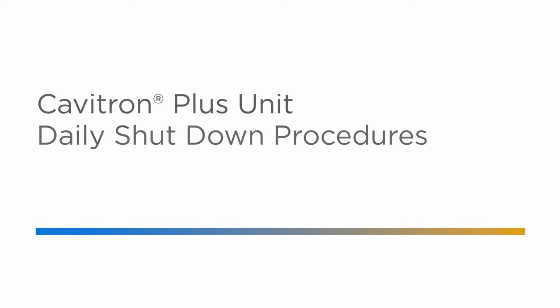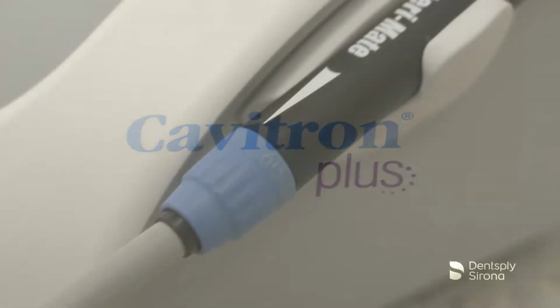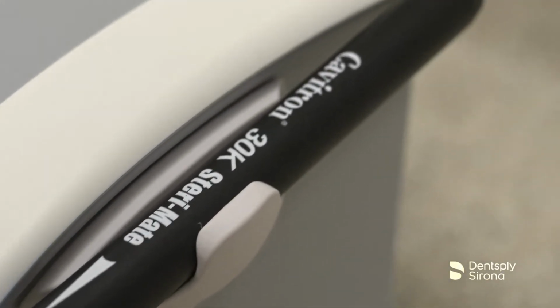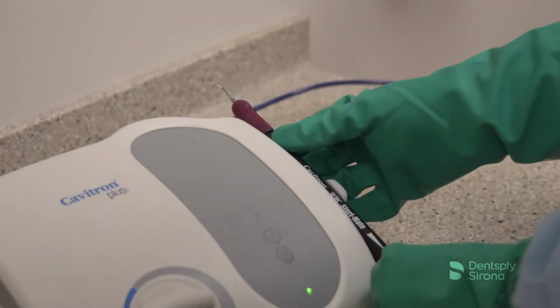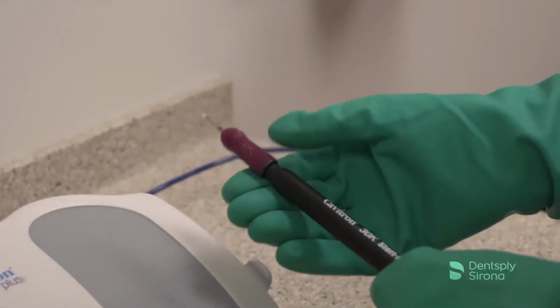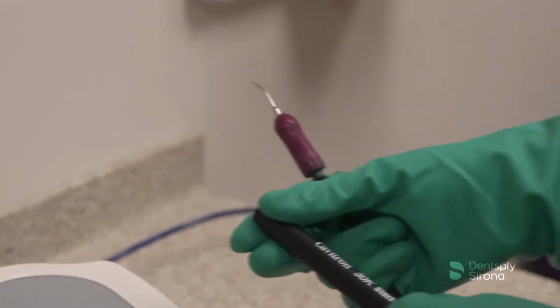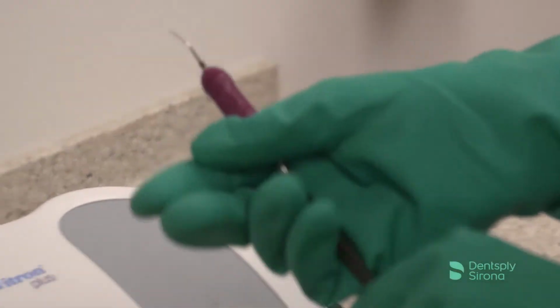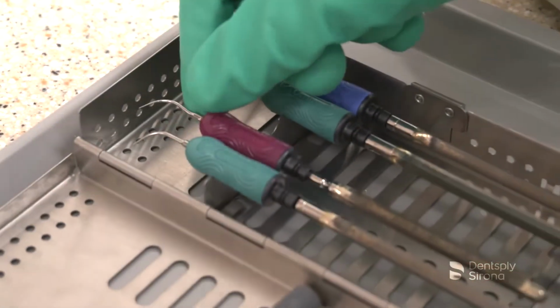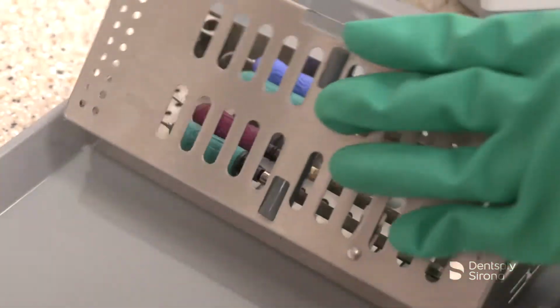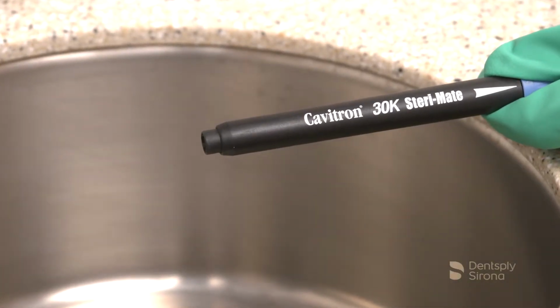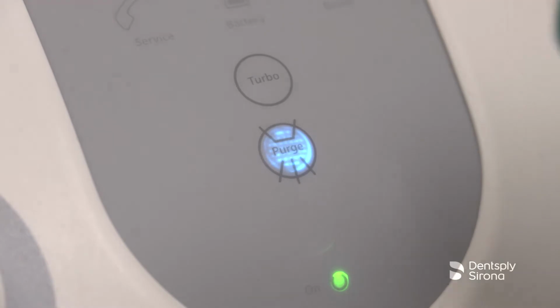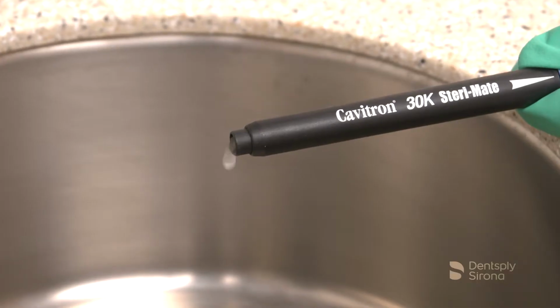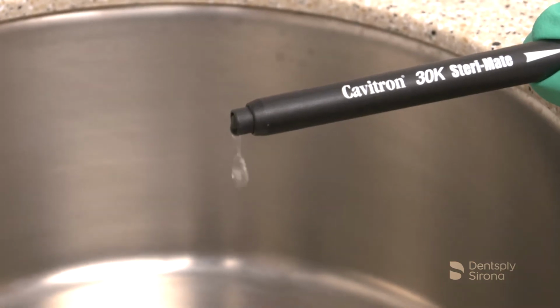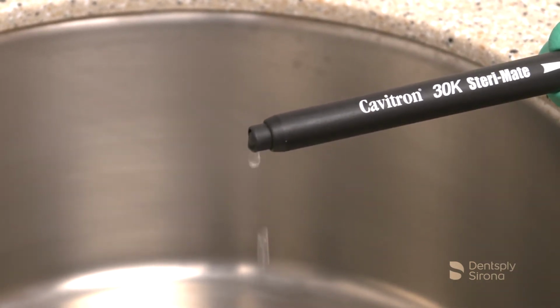After utilizing the Cavitron Plus ultrasonic scaler, it is essential to disinfect all of the surfaces of the unit and its surrounding environment. This important step will reduce the risk of cross-contamination. To begin, remove the used Cavitron ultrasonic insert and secure it in a cassette or transport container. Hold the handpiece over a sink or drain and activate the purge control button. The purge function will run for 2 minutes. This function will flush out any stagnant water that remained in the lines overnight and releases any air bubbles that may be trapped in the handpiece.